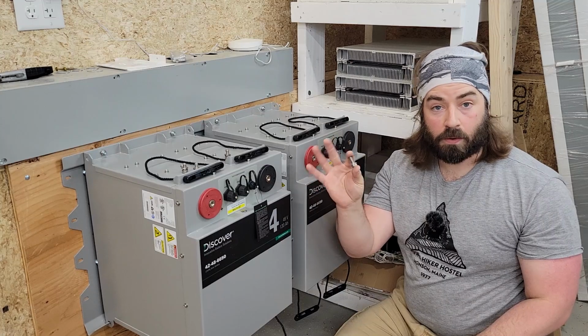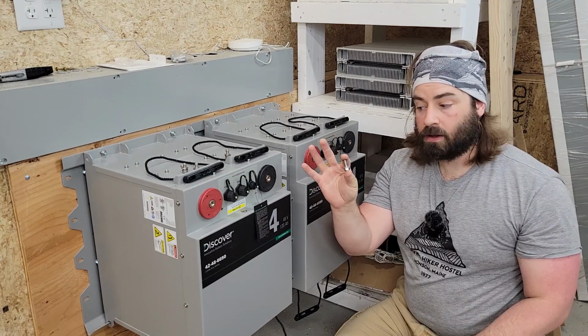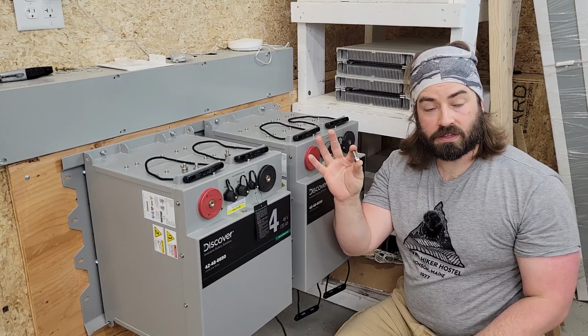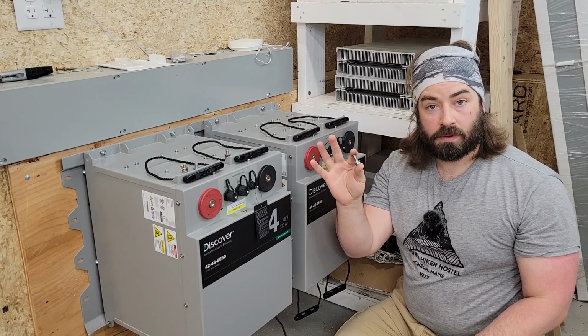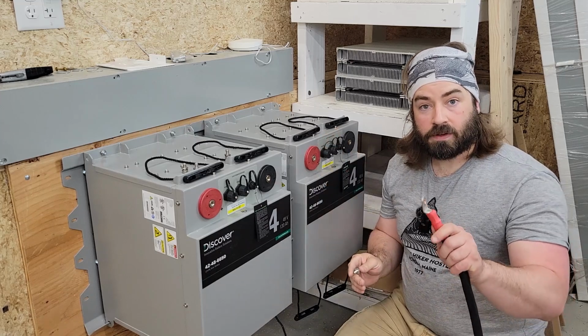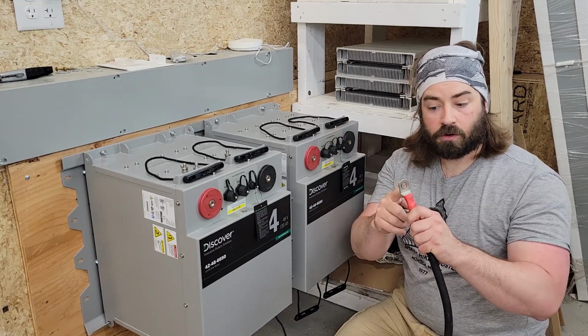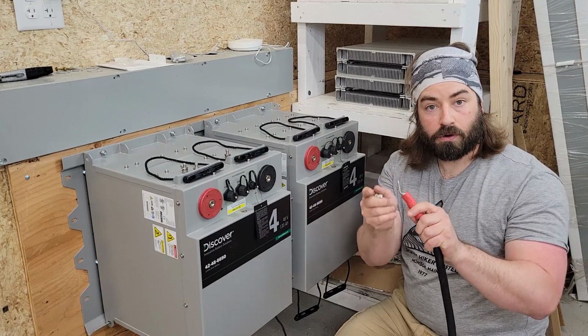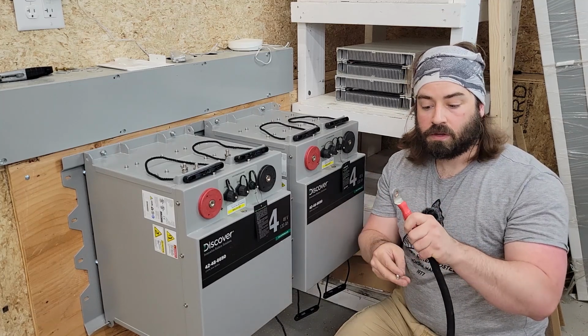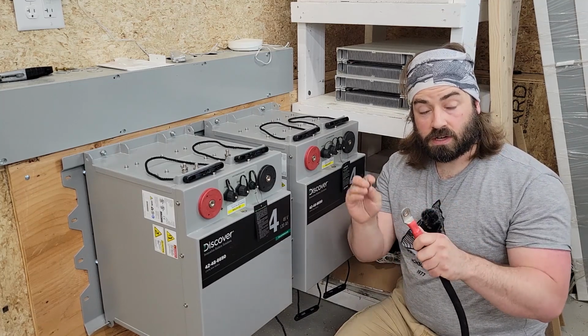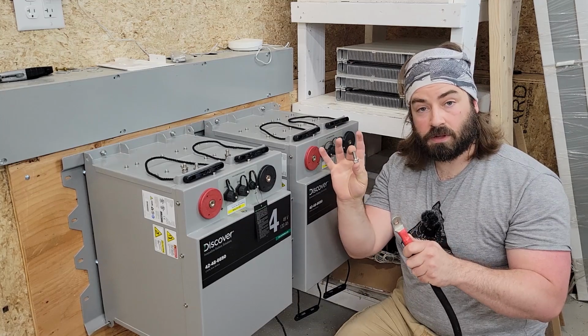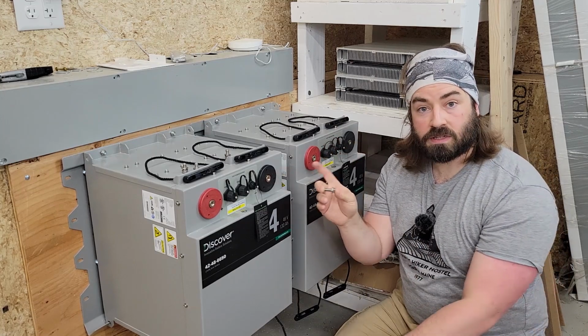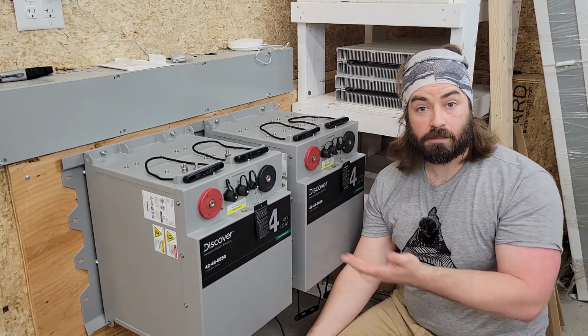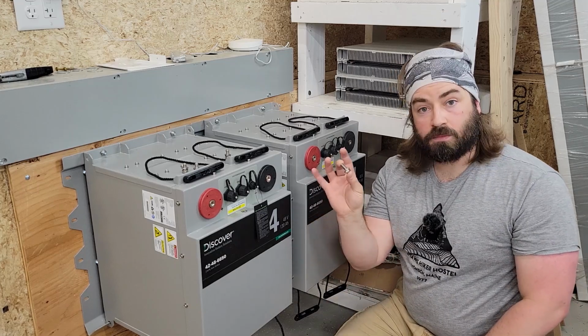These are still M8 by 1.25 millimeter thread, but the thread length on this bolt is about 20 millimeters. We're going to have 6 millimeters taken up with the ring terminals, 3 millimeter thickness per ring terminal times 2. That'll leave us with 14 millimeters. Since the hole is 16 millimeters, as I measured here, I should be fine.